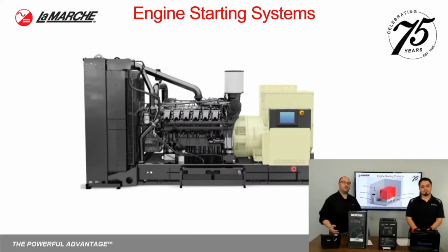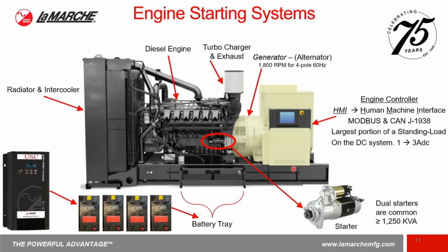Here's a typical generator. This one in particular would be approximately 1000 kVA. So looking at some of the parts here, and again, I don't want to get too much involved in the rest of the generator itself, but it's a good idea to be able to identify some of the major parts, such as the radiator, intercooler, the diesel engine, turbos on the exhaust. This portion is the generator, which is actually an alternator, and most popular in this market segment would be a 4-pole that would be operating at 1800 RPM.